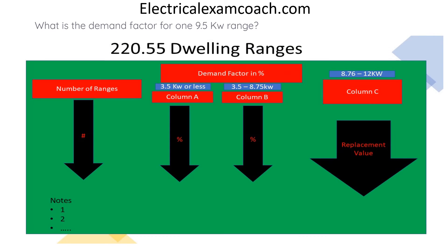To find this answer, we head to table 220.55. The first question we always ask ourselves is: what column does our range fall in? Ours is a 9.5 kW range, so it falls into column C. We start on the left-hand side of the table and find our number of ranges, which is 1. We come over and tee off with the column C value for one range, and we find that it's 8 kW. We have to remember that column C is not a demand factor, but rather a replacement value. So our 9.5 kW range only counts for 8 kW on our load calculation.